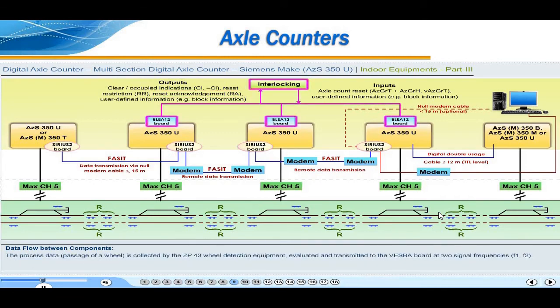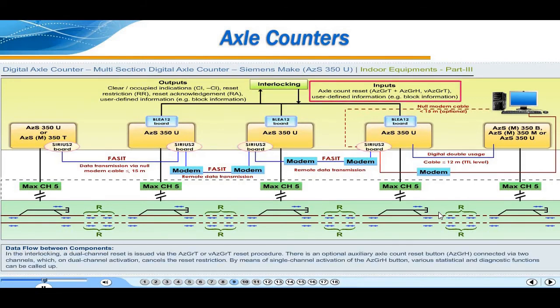The process data, that is passage of wheel, is collected by the ZP43 wheel detection equipment, evaluated and transmitted to the VESBA board at 2 signal frequencies, that is amplitude and frequency F1 and F2. In the interlocking, a dual-channel reset is issued via the AZGRT or VAZGRT reset procedure. There is an optional auxiliary axle count reset button, that is AZGRH, connected via two channels, which on dual channel activation cancels the reset restriction. By means of single channel activation of the AZGRH button, various statistical and diagnostic functions can be called up.